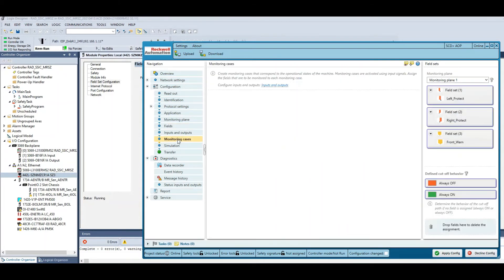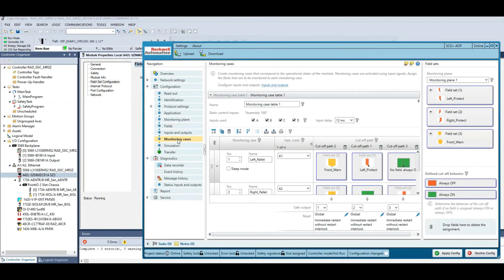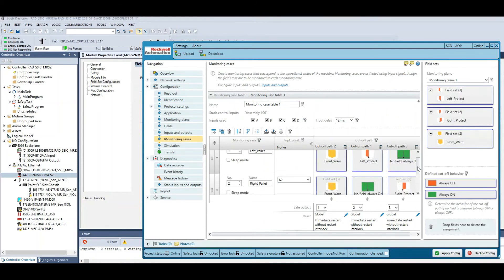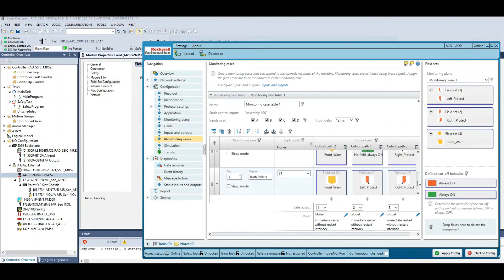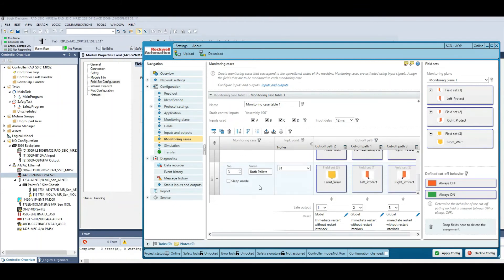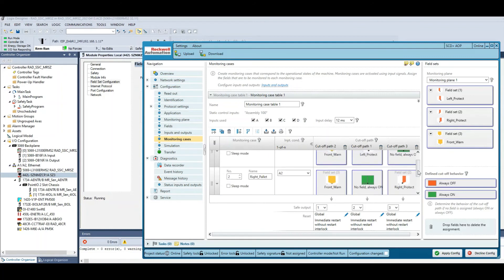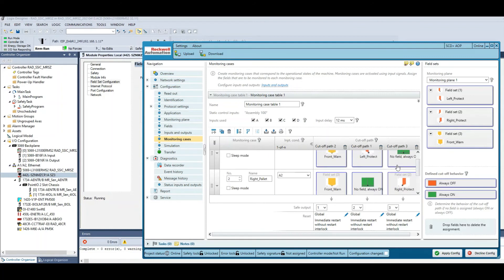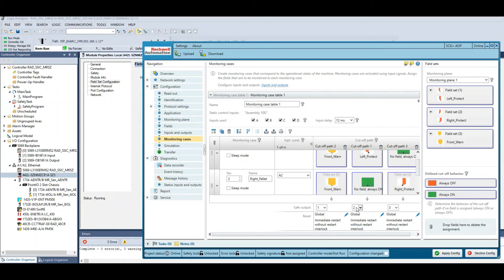And in the monitoring cases is where you configure how these fields are used for the scenario. If you remember from the demo, I had scenario number three protecting both sides of the palletizer and scenarios one and two only protecting one side or the other. Down below the outputs are where you set the outputs that are then used in the safety task of GuardLogix to then protect the machine via logic.